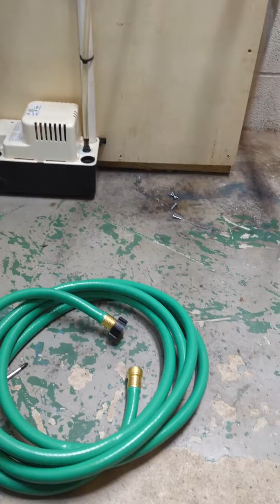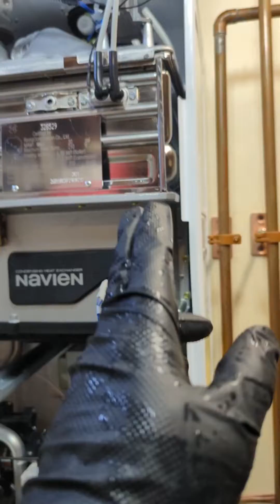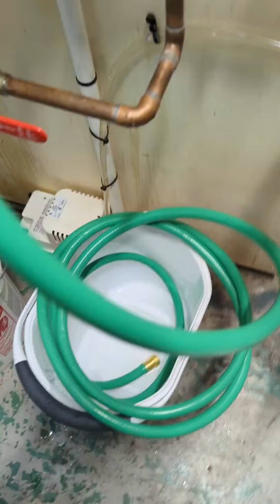When you try to drain the system, hook up the hose on the blue side, because that's the return area, and that connects to the bottom of the heat exchanger. When you open it, it will release the water from that heat exchanger. The red side is the top, and it sucks in air so it doesn't create a vacuum. You gotta open this up so it will just drain. If you do it the other way, it's going to be bleeding water here. So you hook up here for the air coming in, so it doesn't vacuum.